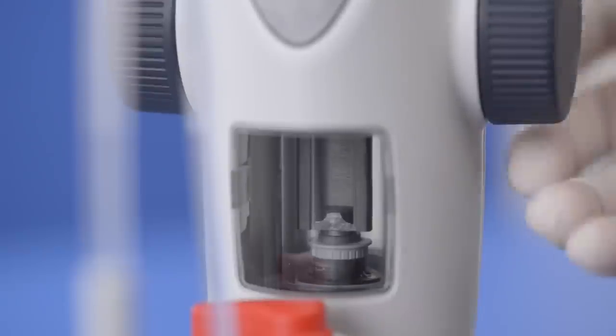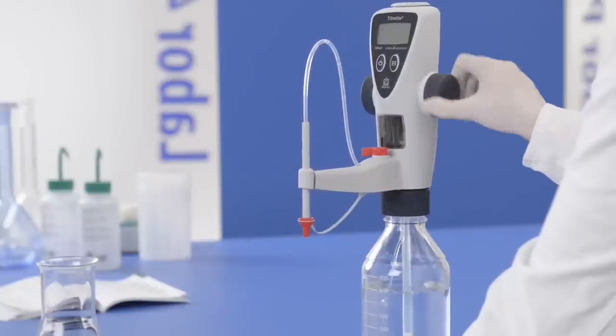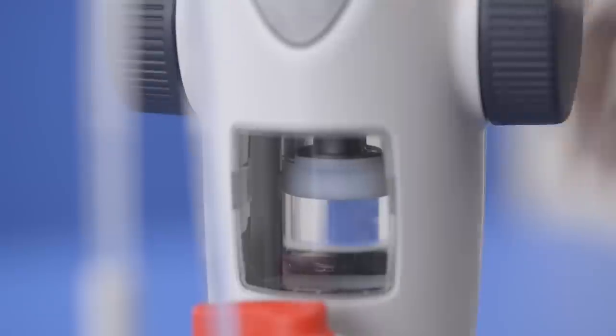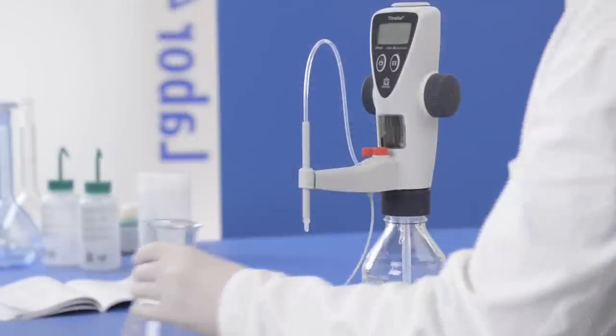Then fill with liquid with a half turn and empty it to the stop in a single stroke. As you can see, the titrant is returned to the bottle. Repeat until there are no longer air bubbles present.